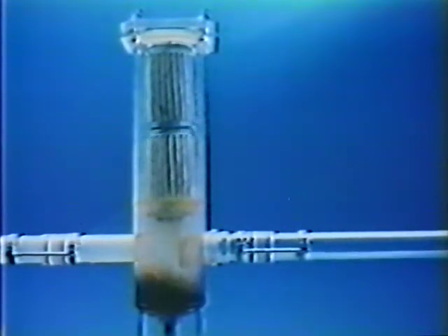With a view to attaining absolute protection, laboratory tests have been carried out using models to ascertain whether any condensate that has managed to slip through can be caught in the dust filters installed at the beginning of the meter runs. Condensate was found to collect in the dust filter pot at low gas velocities. At higher gas velocities, however, the liquid inside the dust filter pot behaves so wildly that it's forced out again right away.